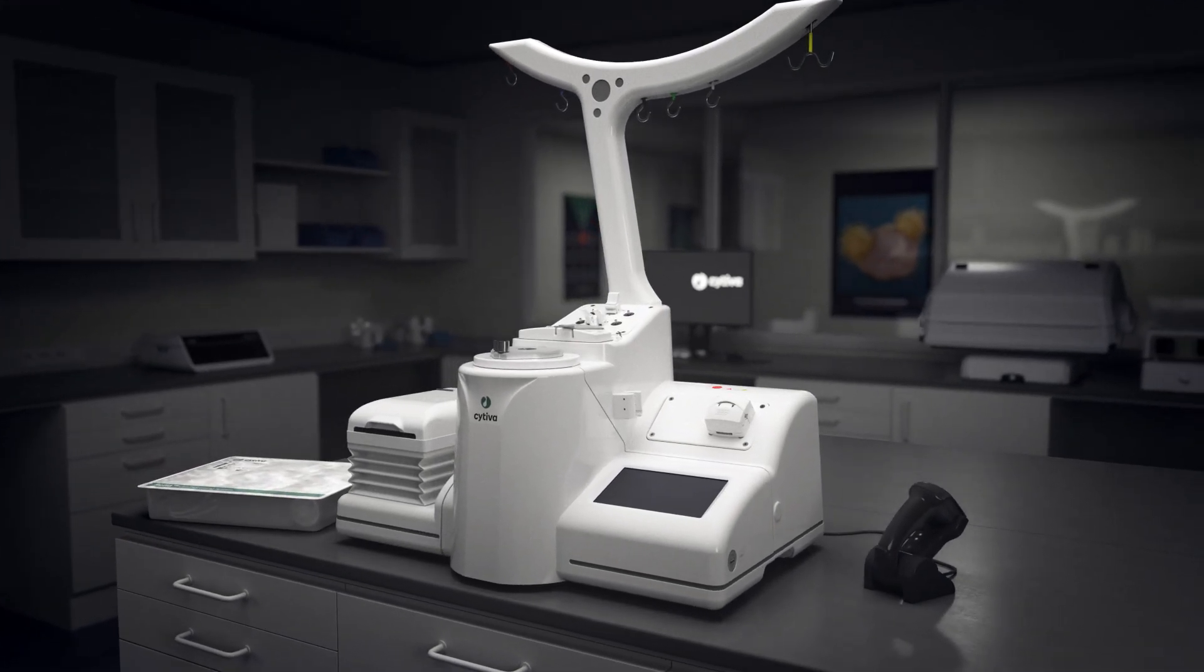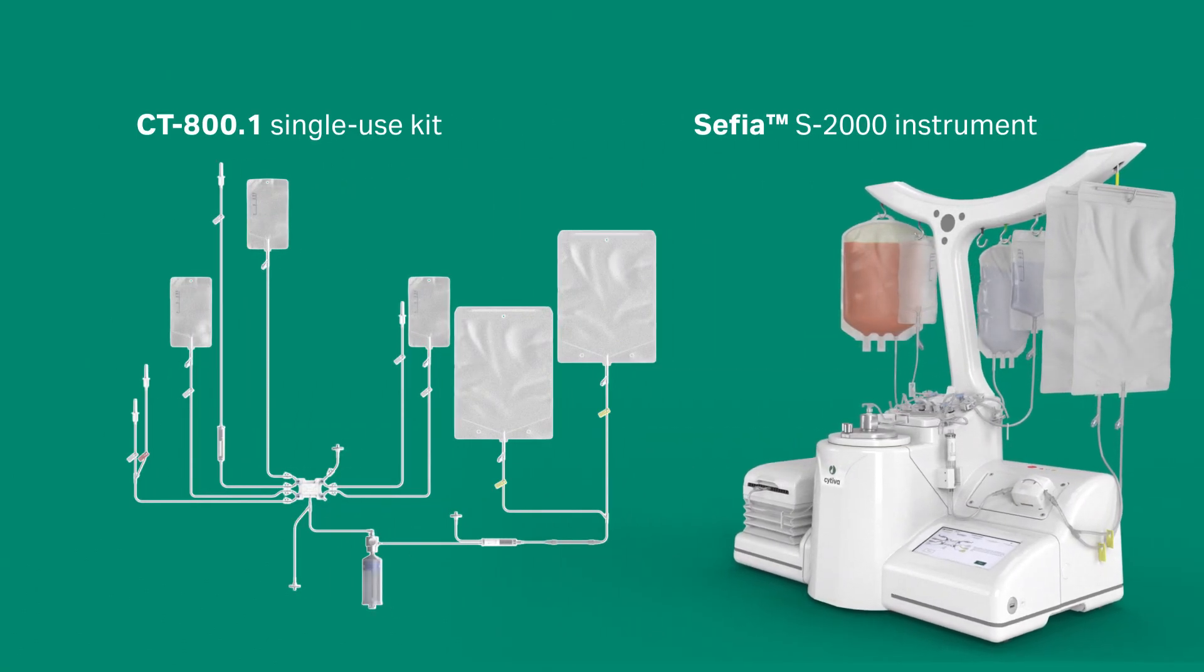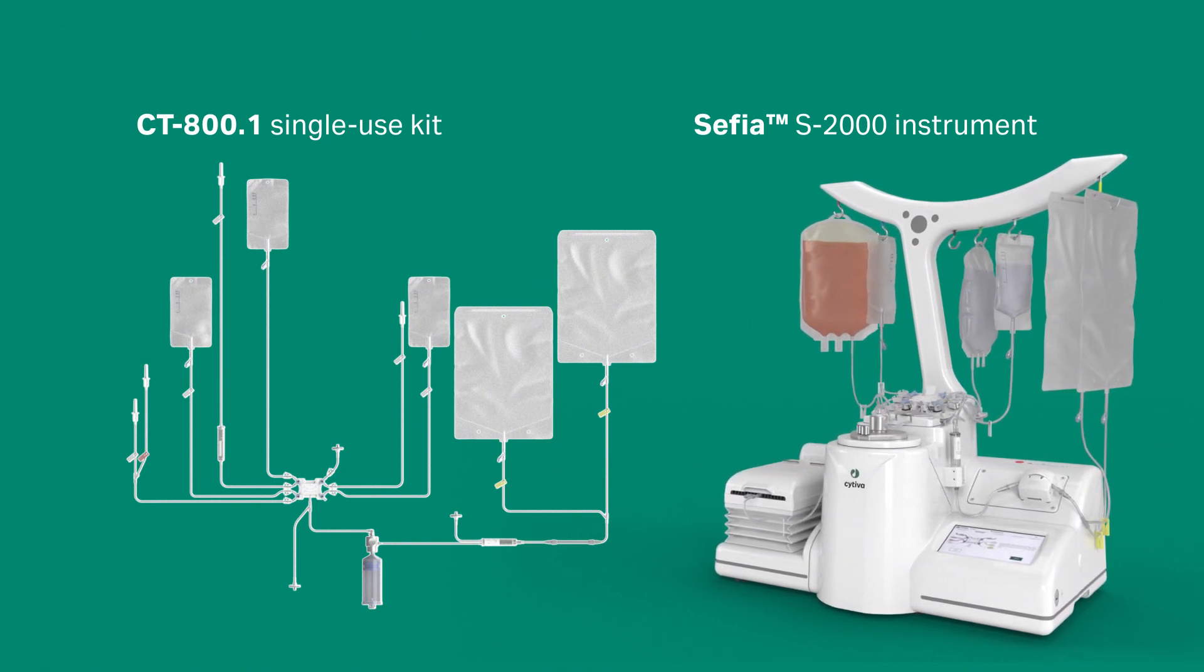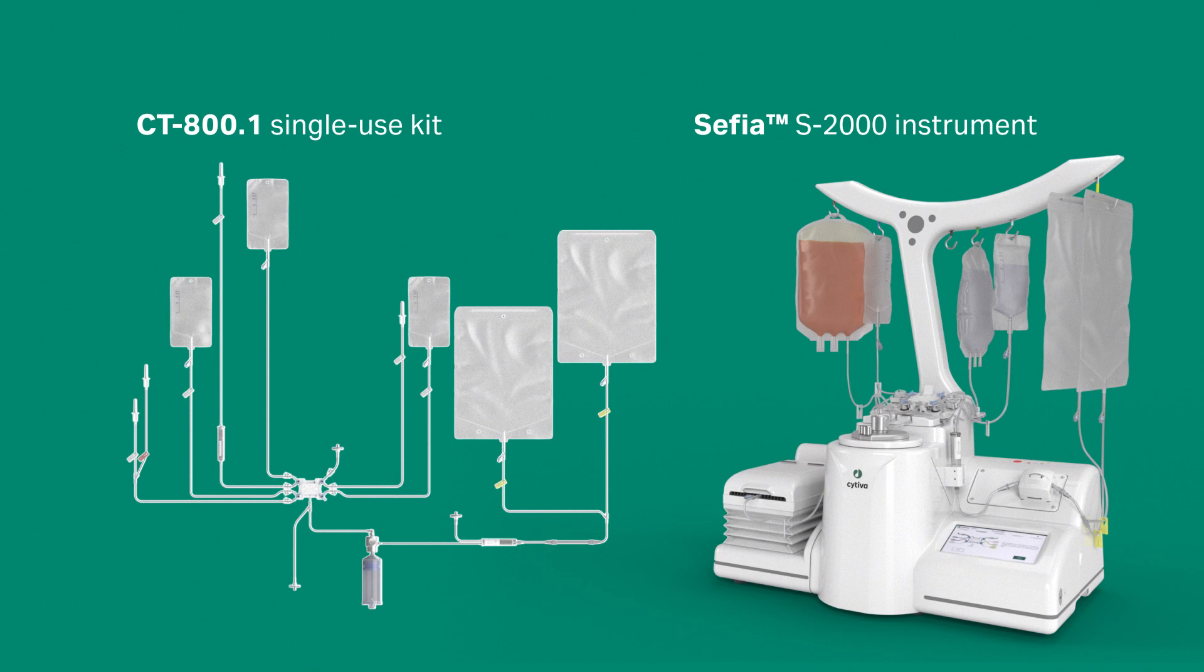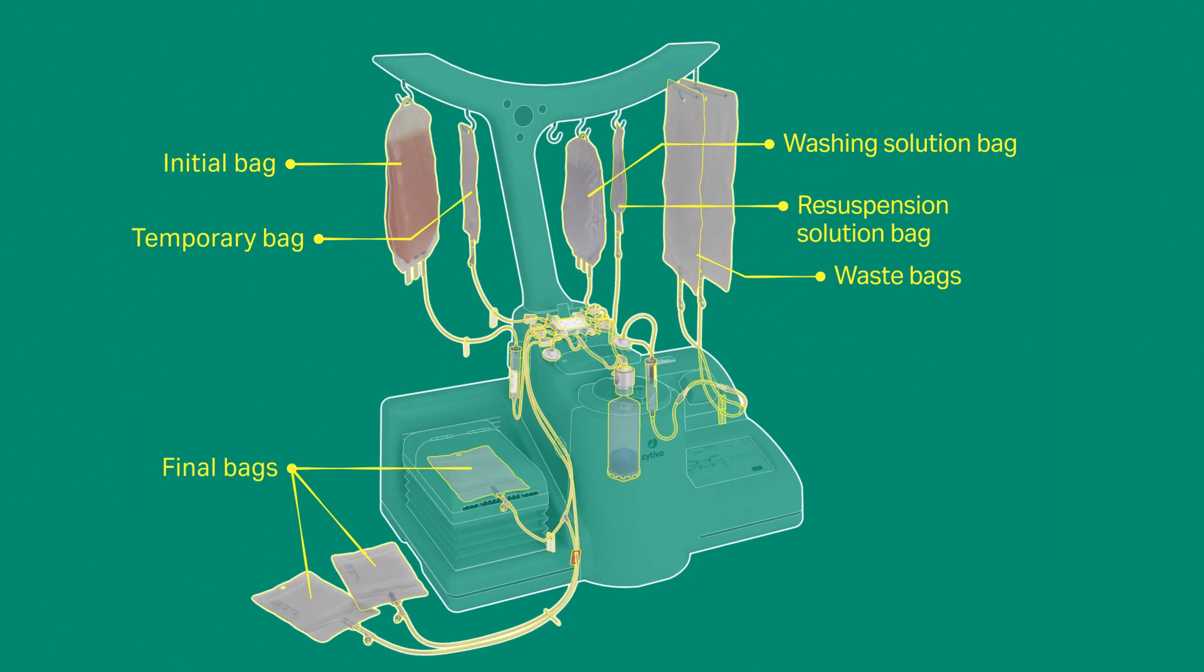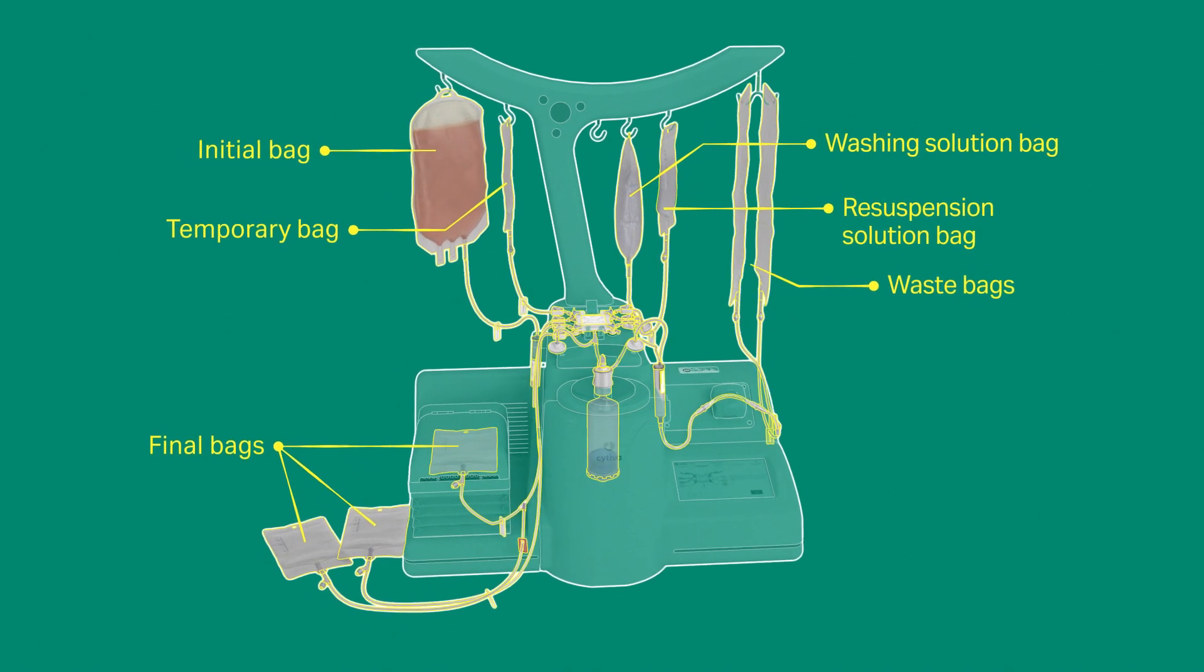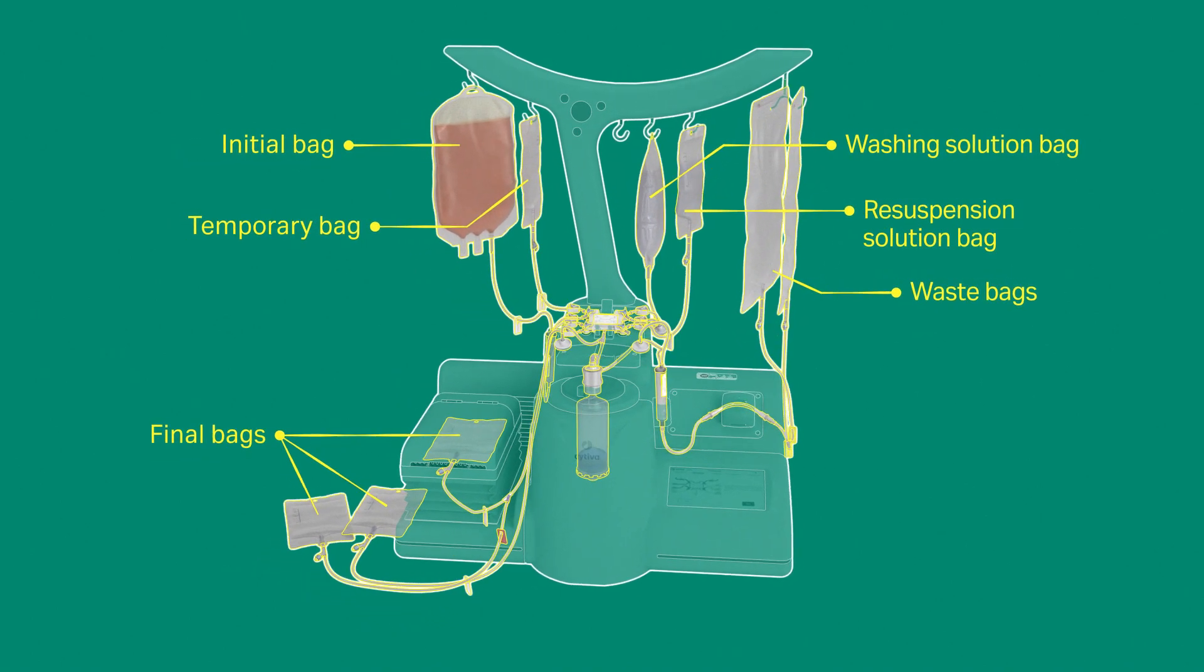FlexCell uses continuous flow technology by combining the capabilities of Sefia S-2000 cell processing instrument and CT800.1 single-use kit. You can concentrate up to 10 liters per hour thanks to the system's peristaltic pump and separation chamber design.